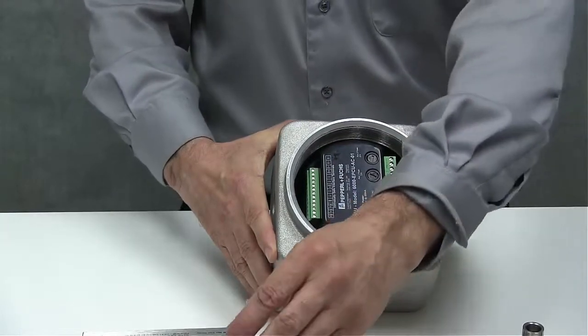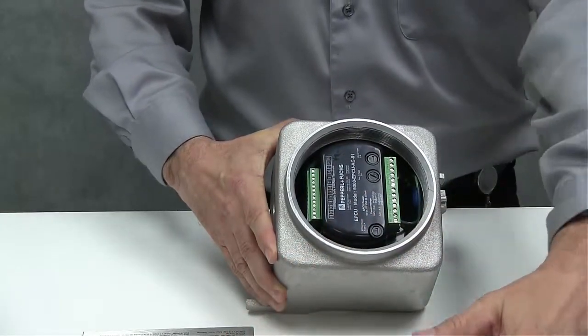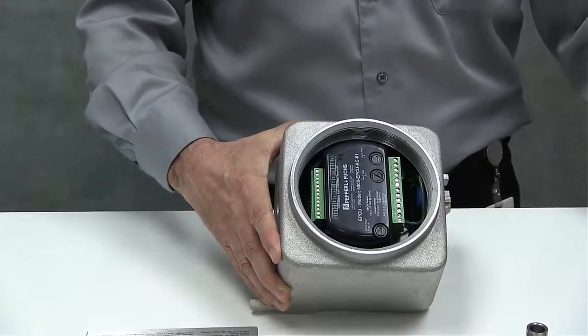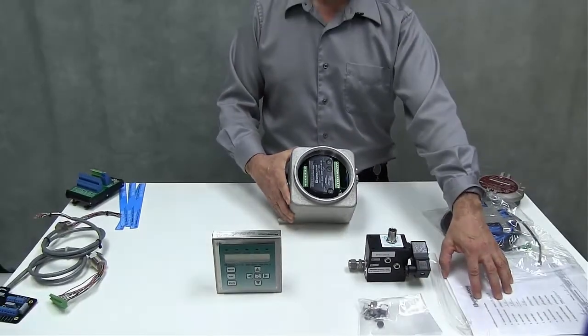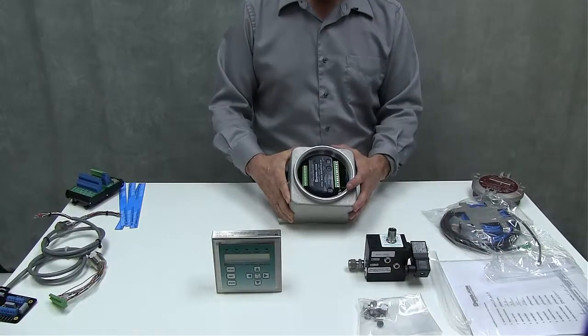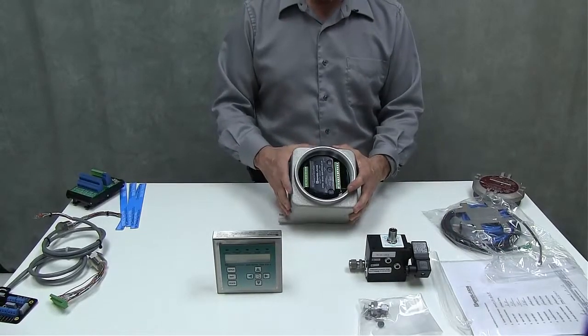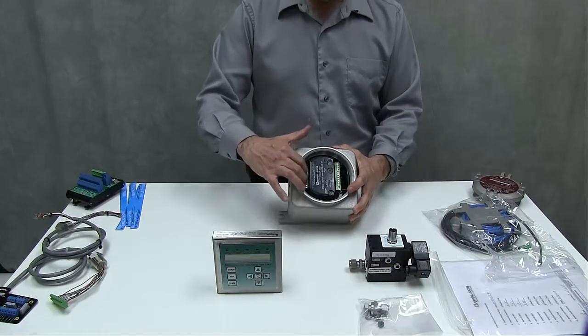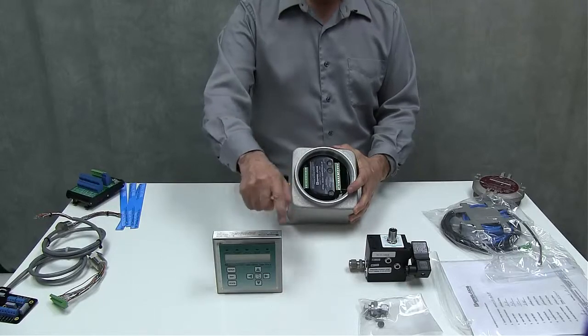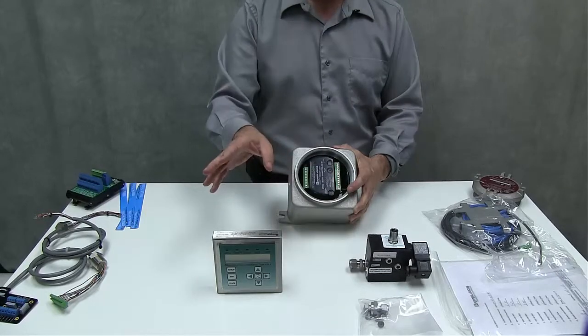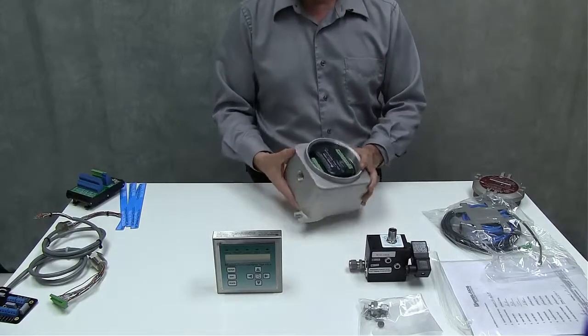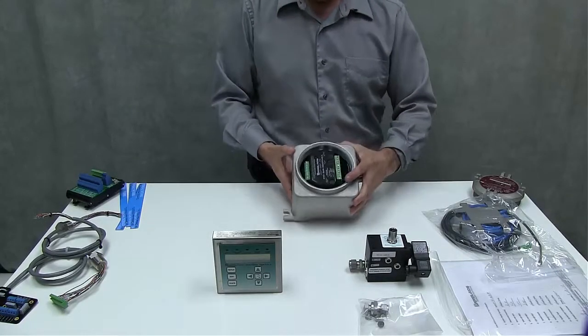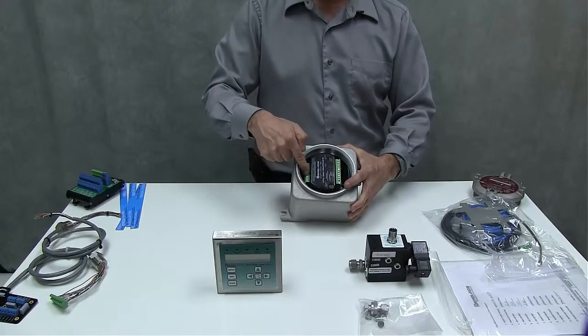Along with the component kit you get the user interface, the solenoid valve with some mounting hardware and some other mounting hardware with cabling and a manual on how to operate the system. The problem is with the component kit all this field device wiring from the IS termination board, the solenoid valve, the vent and any type of inputs you have coming in have to come in through this cable gland and have to terminate onto these terminals.